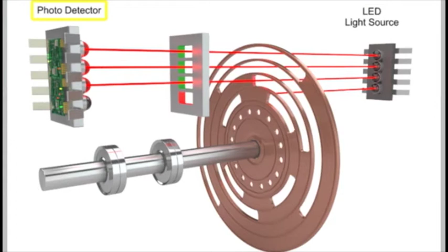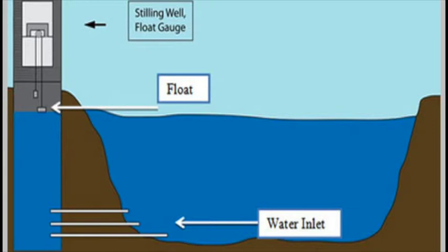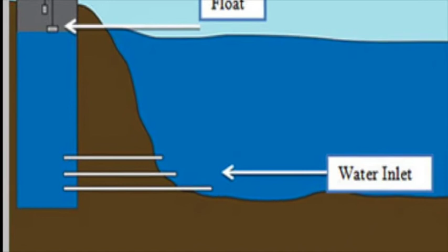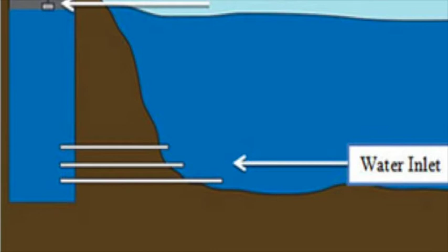Shaft encoder type measurement: the most common method of measuring water level is a stilling well equipped with a float and shaft encoder. The components of this type of gauge include a stilling well, inlet pipes from the water, float, tape, wheel, and shaft encoder, which electronically sends signal to the data collection platform.